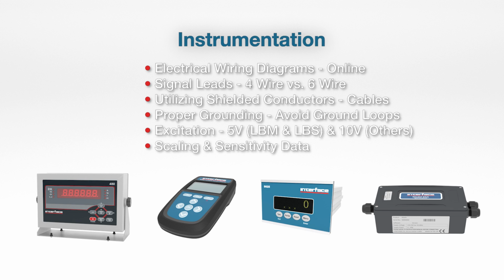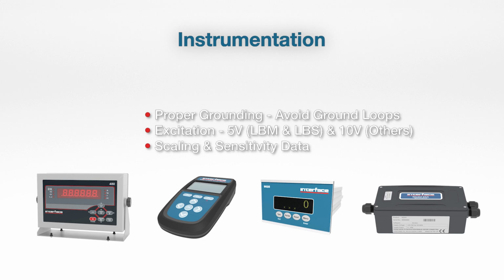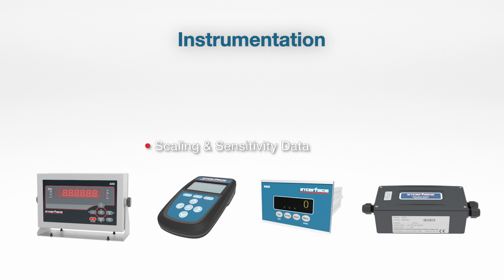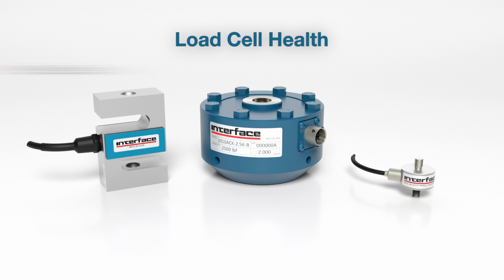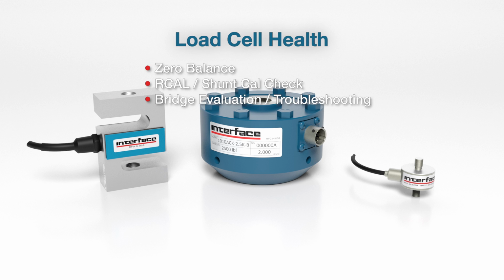The bottom line is you're going to be referencing that calibration certificate in some way to get scaling data off there. Lots of options there. Now, once you get hooked up to the instrumentation, you can do some further diagnostics on the load cell, particularly if it's an older unit. There's a couple things you can check to establish the health of the load cell.